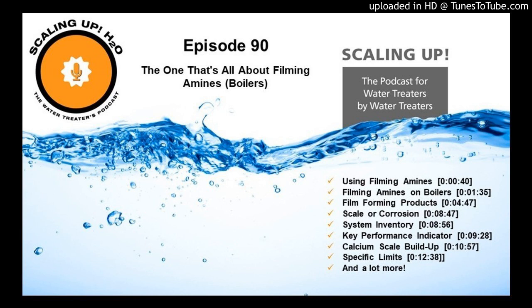However, fast forward to later in the day, and your boiler has been running and your filmers have been filming and going up into your steam lines and performing the functions that we now understand them to perform. Maybe you catch a boiler sample and it looks like there's nothing in there, and you think, oh my gosh, I need to turn my pump up. Well, maybe. But what is your system filmed? Is there iron in your system? Maybe you don't need to turn your pump up. It's just that it's already gone and done its job.